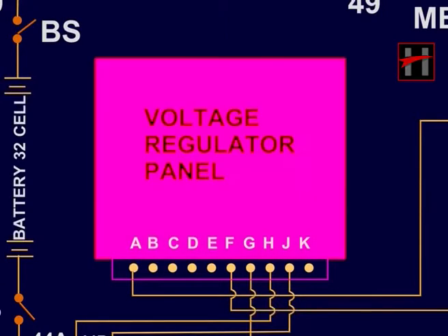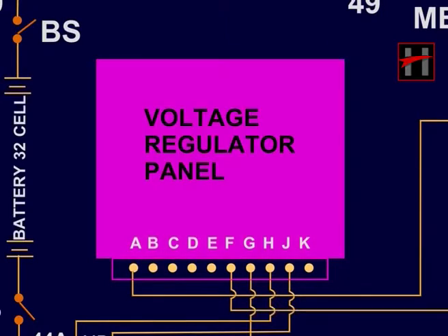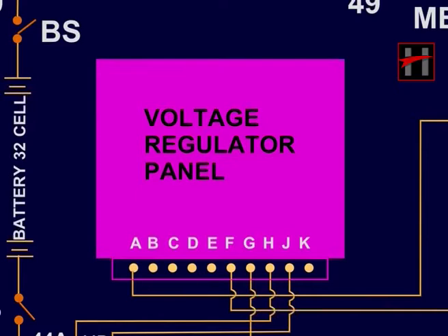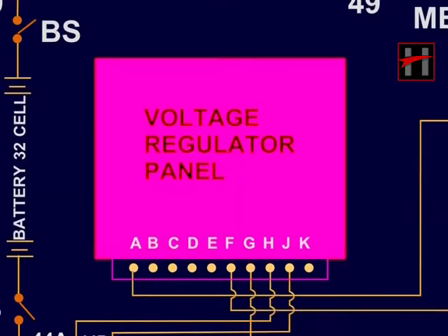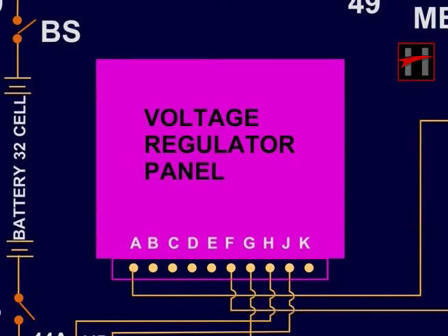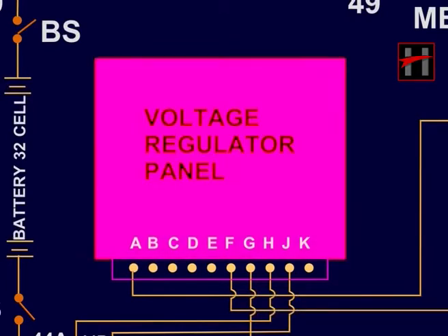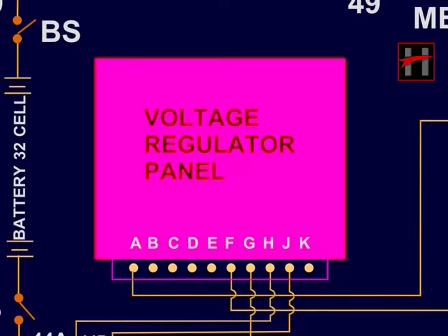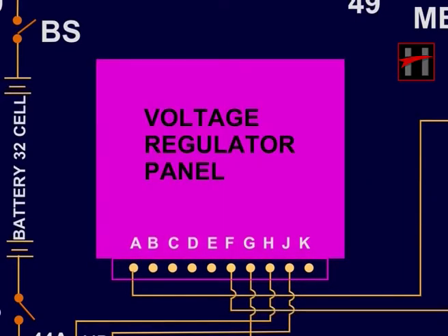The regulator card supplies the pulses necessary to turn on the silicon control rectifier VSCR1 located on the BX card. Card BX is called the power card. The main silicon control rectifier VSCR1 and the additional circuitry necessary to turn the SCR off after it has been turned on is mounted on the BX card.